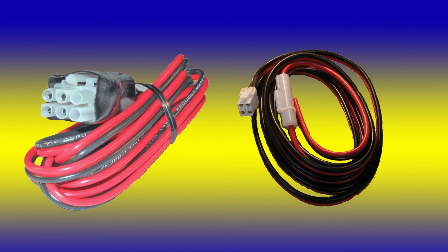If we subject the cable to a load of 100 amps, where the fuse would normally require 3 seconds to open, our voltage drop would be 2 volts and our wire has to sustain 200 watts of dissipation.